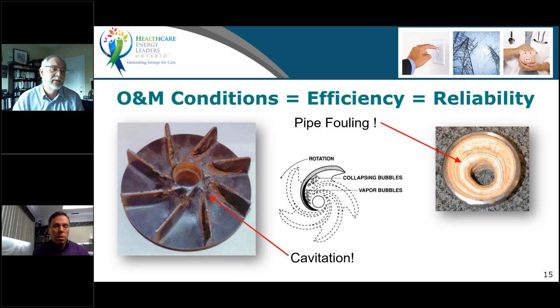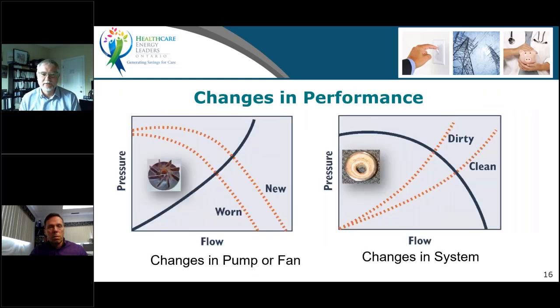It was funny because I found that piece of metal on the electrical maintenance manager's desk, and he said, I got this because they wanted me to put a bigger motor on this pump, and I said, there's something wrong here. So we cut the pipe apart, and we discovered that it had nothing to do with the pump. It had everything to do with the pipe itself. So ultimately, we can change those system curves when we change the system. A dirty one will exhibit a steeper system curve, and these are all for closed systems.